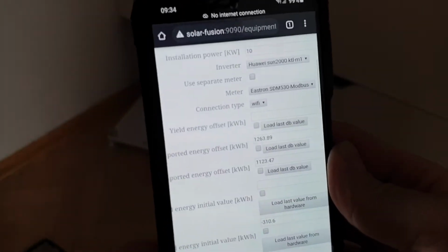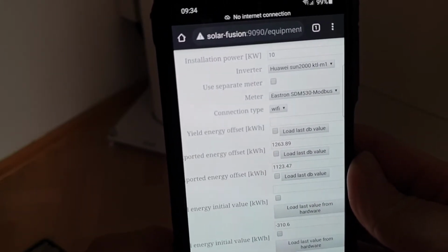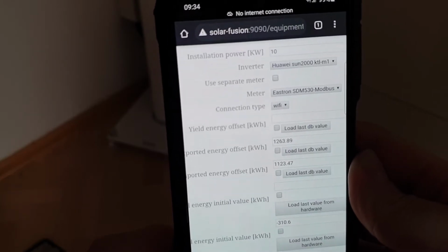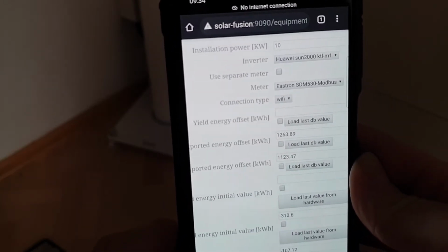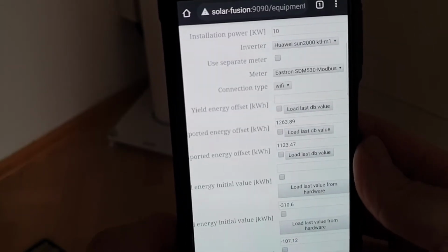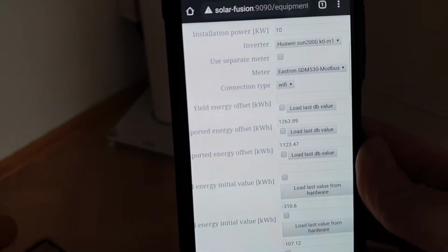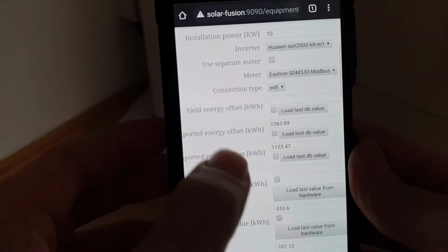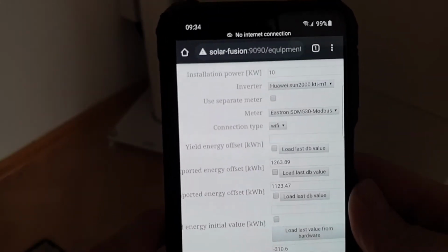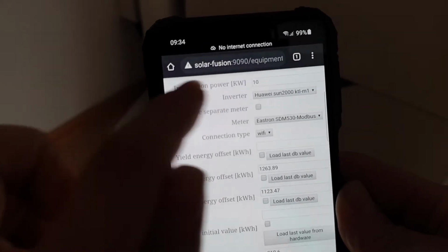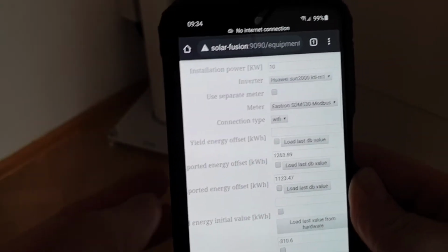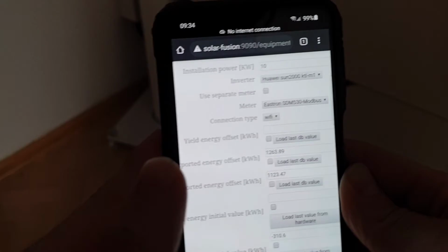I had that situation when those readings from Modbus from the additional power meter, Eastron SDM530, had been incorrect. So I got a spike on the exported energy. It had been a real spike of a few megawatt hours. So I chose to verify that kind of data. So I've added that installation power and that file with ranges for each metric.